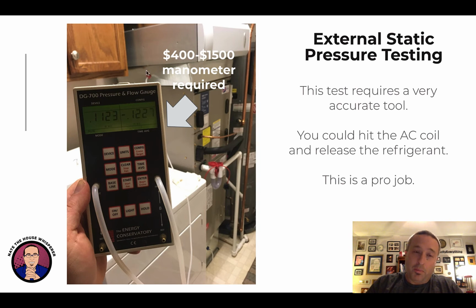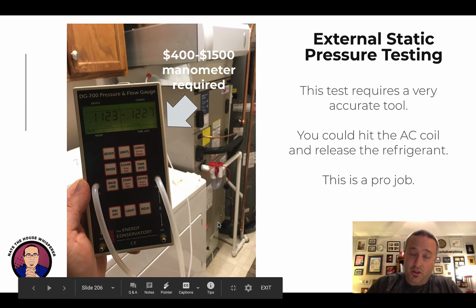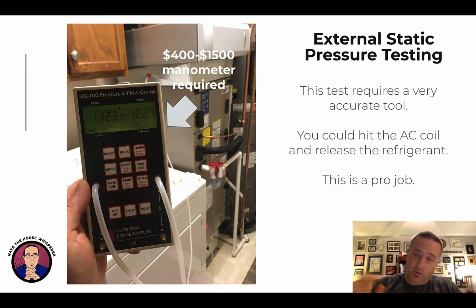This is not something you really want to do yourself, because it requires this accurate tool. You also need to drill a bunch of holes into your system, and particularly when drilling near the coil or the heat exchanger, bad things can happen. You can release the refrigerant, which is not something you want inside your house. You could drill a hole in the heat exchanger and cause a carbon monoxide risk. So this is a professional job. Important note, so I will tell you stuff that's DIY-able. Heat pump water heater, if you're advanced, go DIY that sucker. But this, be careful, it still makes me nervous when I do it because I'm not a tech.